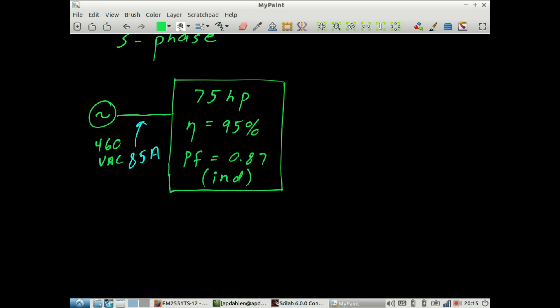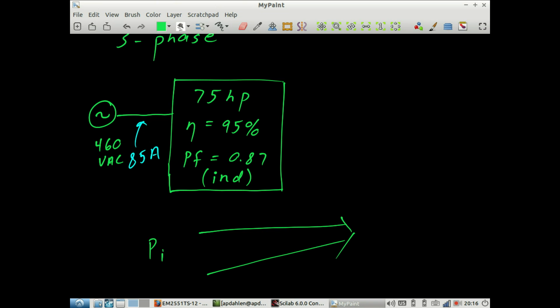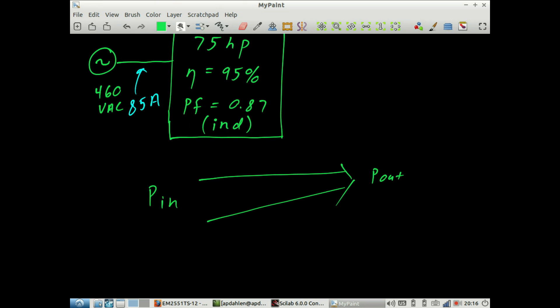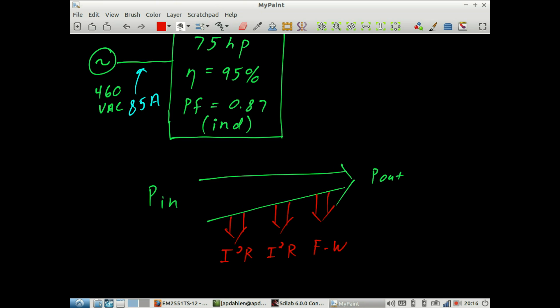We'll start this process by looking at a power flow diagram. Here we've got power in, we've got power out, and we have some losses along the way. There's some I-squared-R losses in the stator, some I-squared-R losses in the rotor, and then there are other losses such as friction and windage. Recall, this is a big motor — it does have a fan, and it takes energy to push that fan around.